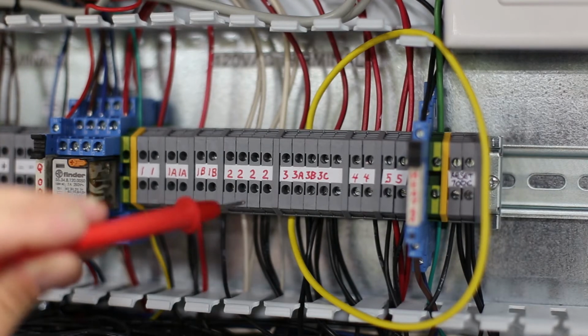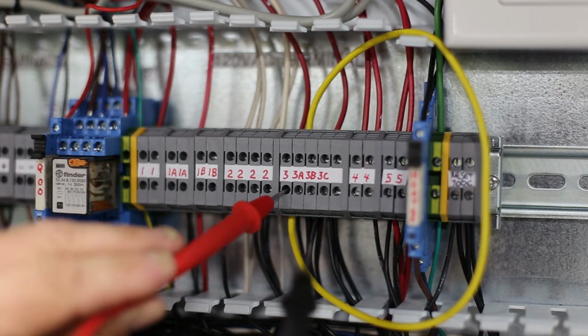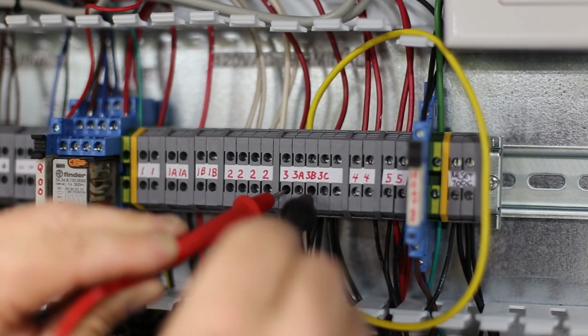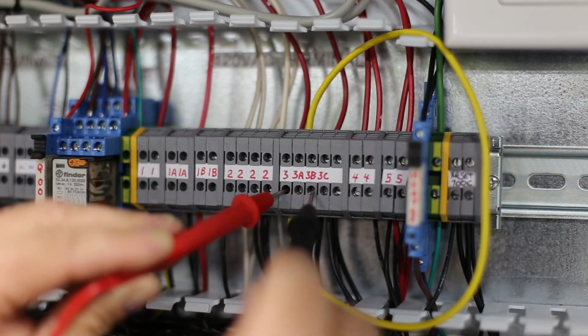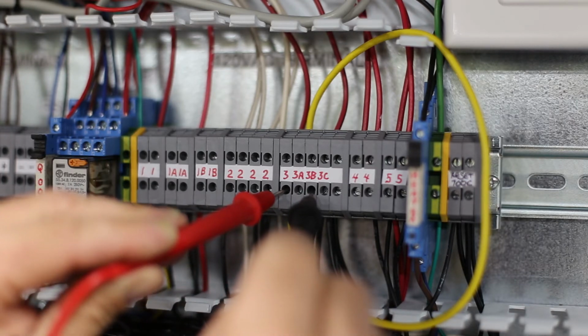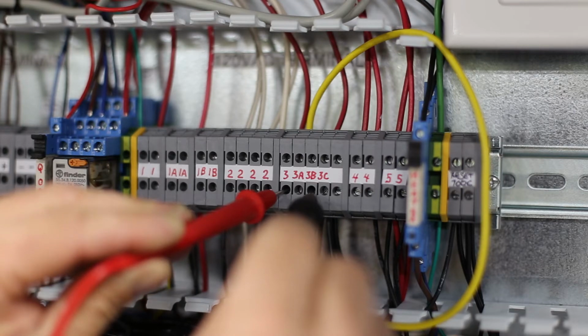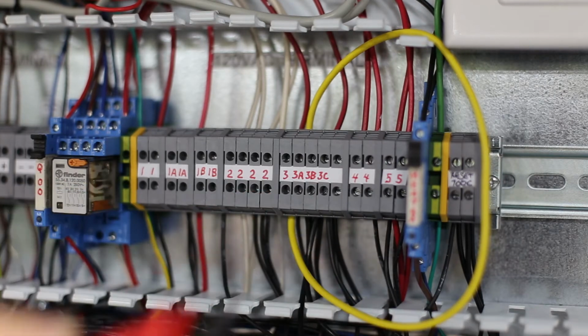If one of these is missing between 3 and 3B, what we do is we go to our electrical control circuit page and look and see what 3B has for a contactor on it, and then we go check the e-stop that makes that happen. Now a lot of times it's either going to be a gate switch or an e-stop on the control circuit panel, or an e-stop on the front section of this 990.